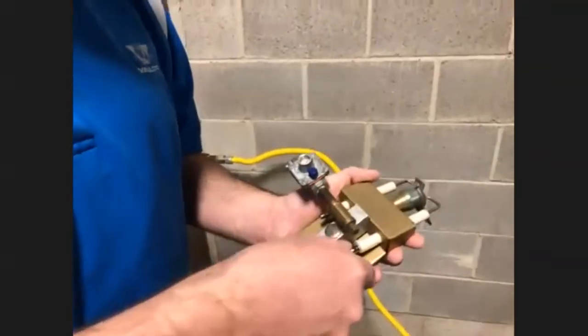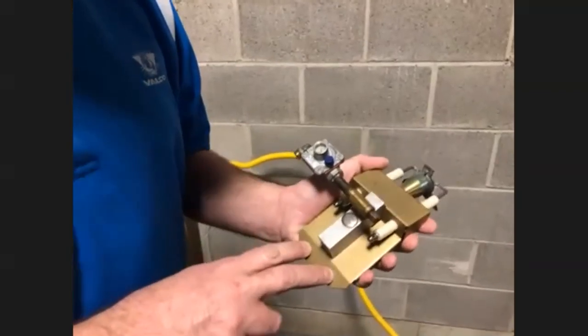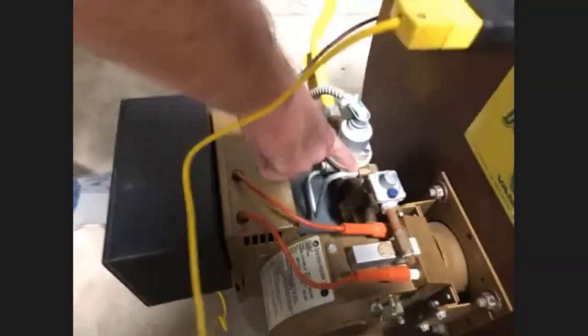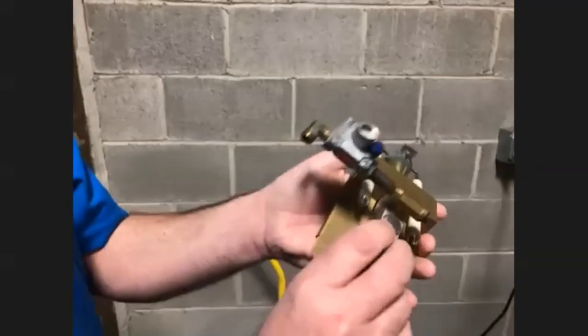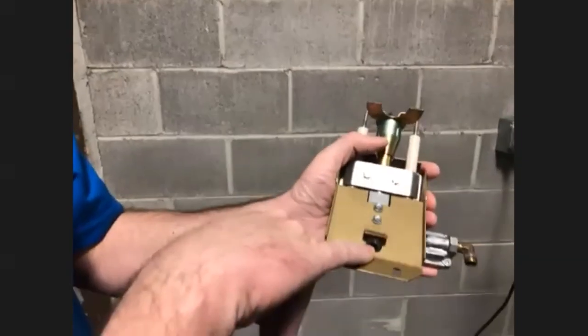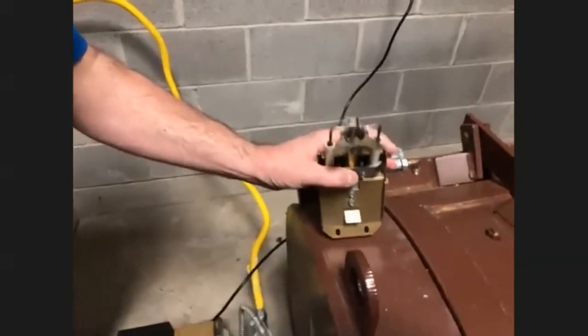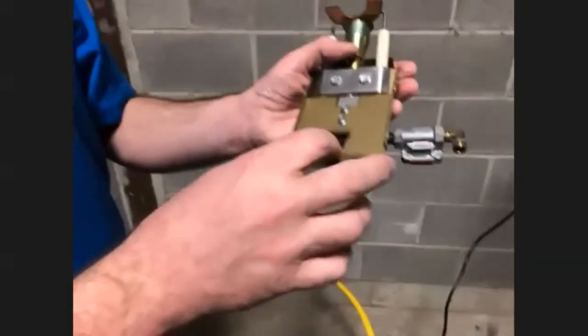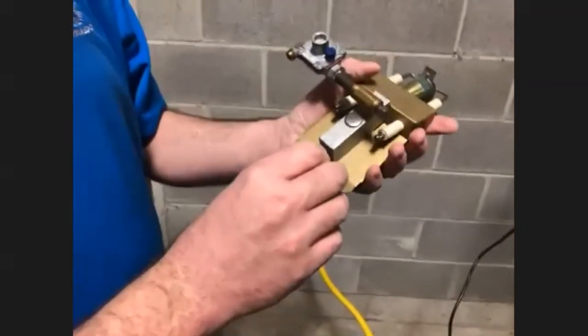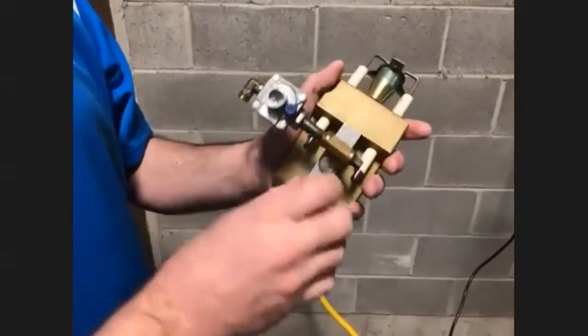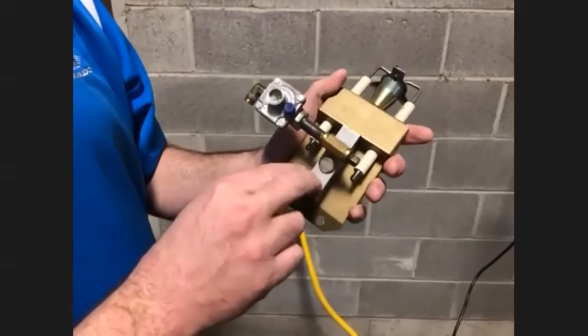What you can do is, again, you take this unit off, you disconnect your ignition cables. There are two screws, as you see right here, that hold that to the housing. Loosen those up. You must loosen your gas connection right there, and you take it out, and then here's your igniter assembly. As I flip it over, you can see there's an opening right here. What I found at times, just do a very light tap on something. There may be just a particle of dirt or something inside there. See if it will come loose and fall out. You want to make sure that everything in there is clean. Again, it's a small orifice assembly in there, so if there's any dirt, it will plug that up.